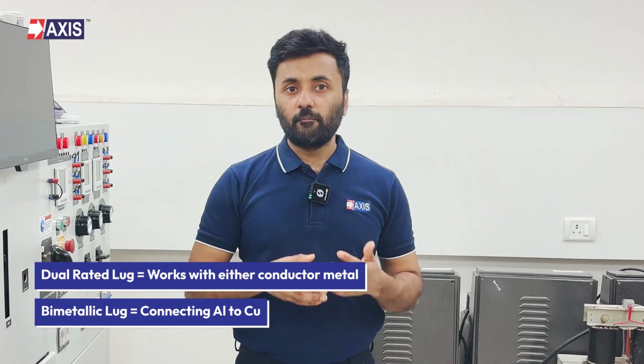But please note, a dual-rated lug is designed for a specific conductor size range. If the lug body is aluminium, it can accept aluminium or copper conductors within a specific range. But the copper conductor must be sized according to the lug's rating, not just the same cross-section as aluminium. If you use a copper lug body for an aluminium conductor, it works, but copper lugs cost more than aluminium lugs. So you pay extra for the lug material even though you are connecting aluminium cable.